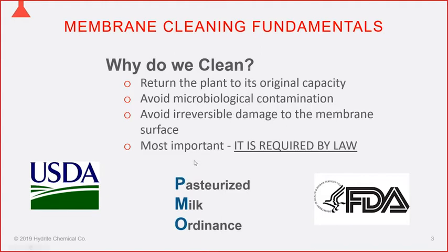When we clean, we want to return any membrane plant to its original capacity. What's mainly different about membranes compared to other systems in your plant is that we can't really open up a membrane and inspect it for success or failure in cleaning. We have to take it as a leap of faith and look at certain aspects of the system to judge whether or not we were successful.